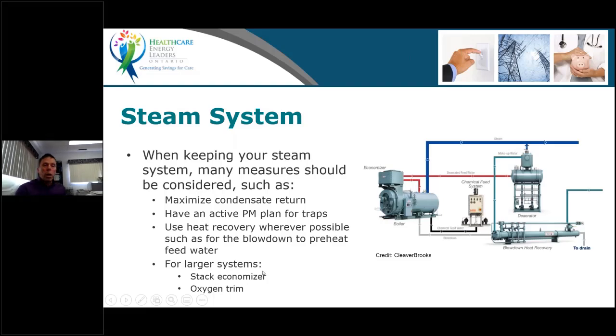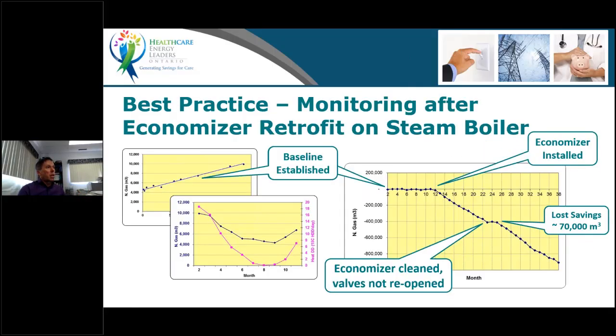Stack economizer, that's one way to recover the heat going out the stack by putting a heat exchanger in the stack that will preheat the boiler feed water. So again, typically seen in larger installations. And you can also recover what's called blowdown heat. The boiler has a system to clean its water. I'm oversimplifying here, but you can also recover some of that energy instead of it going down the drain, which you often have to quench with fresh water. So there are a lot of opportunities for savings when you have a steam system. But if you have to prioritize, start with steam traps.